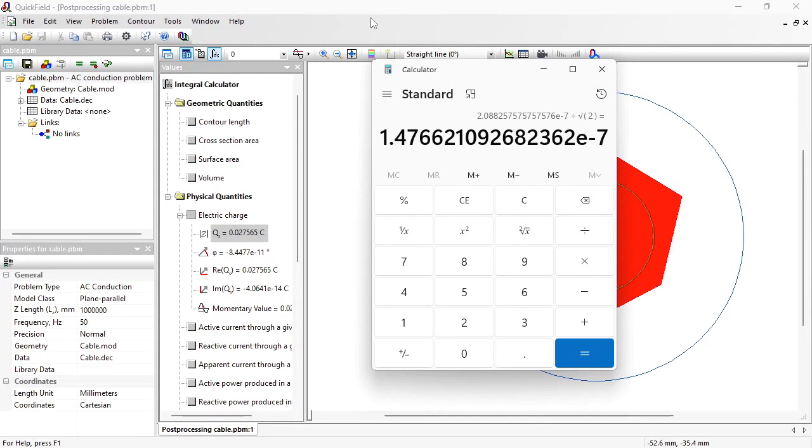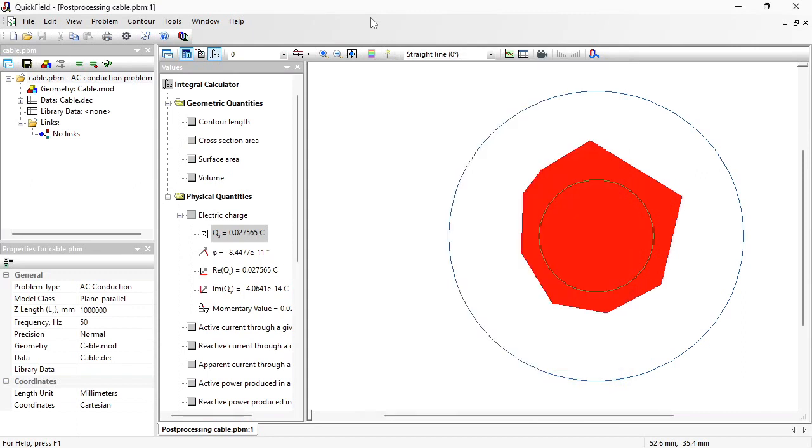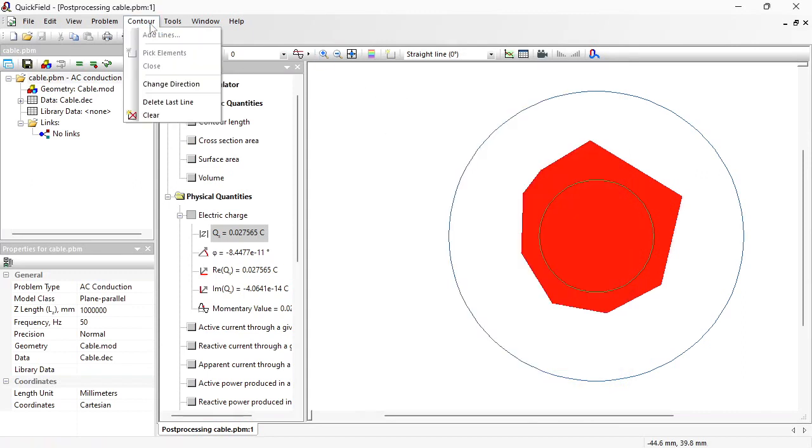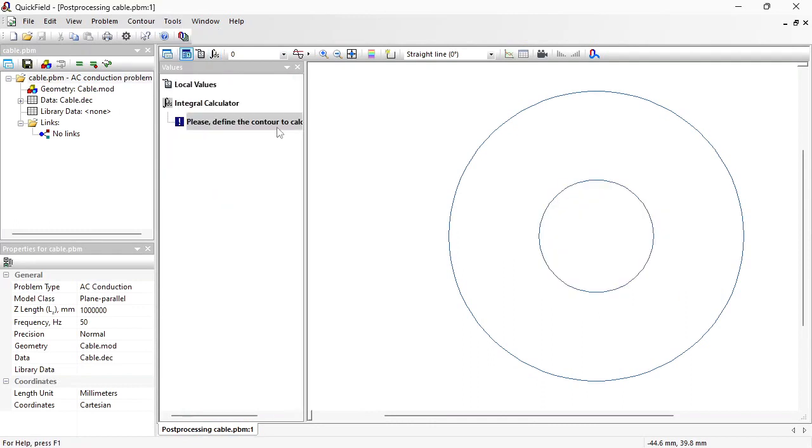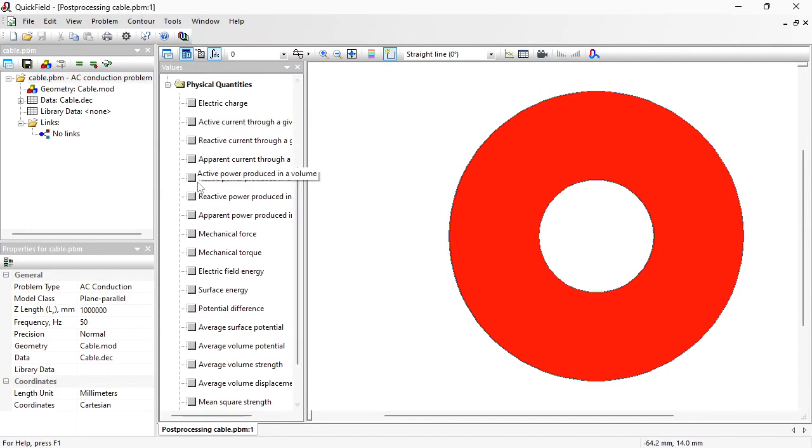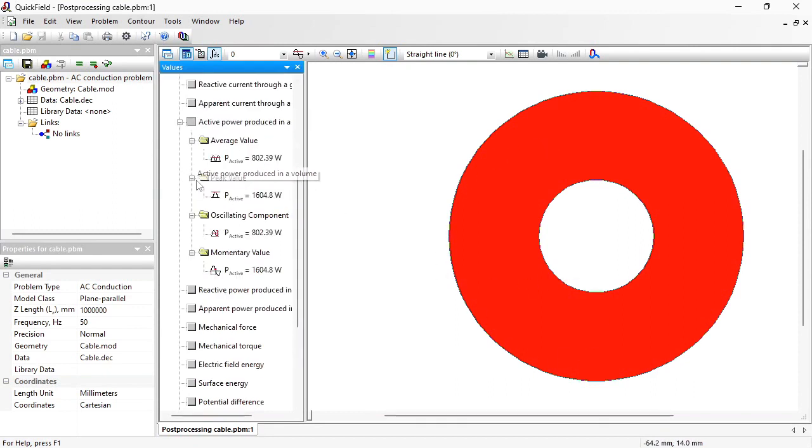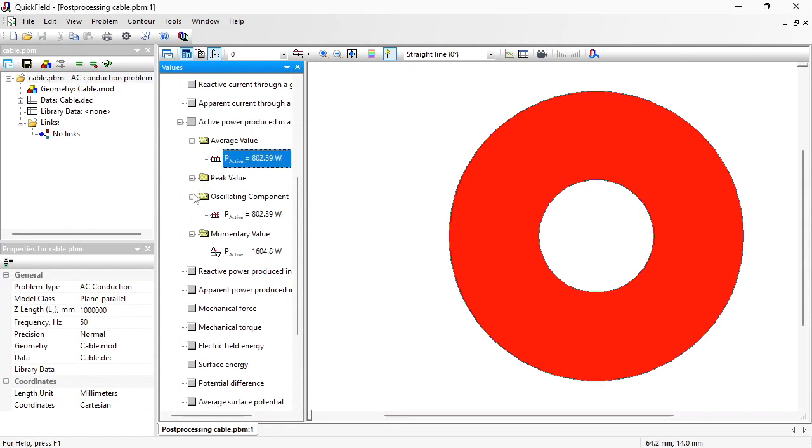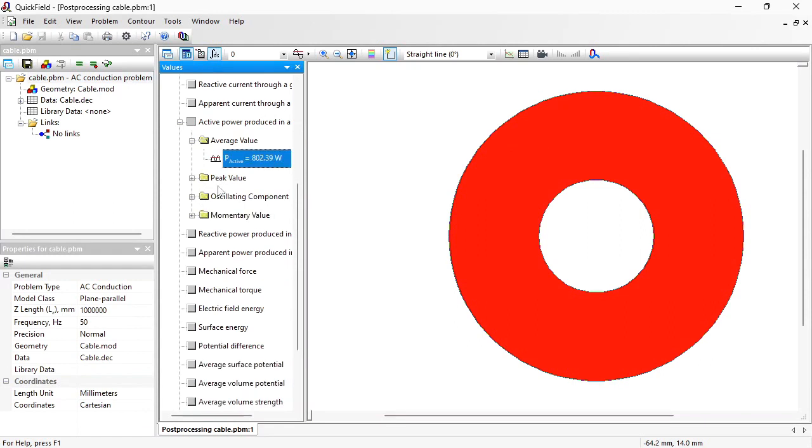Now let's calculate the losses. Again I am going to use the contour tool. But this time I will select the insulation. Click to select. Go to the integrals. And this is the active power produced in the volume. Again this value is calculated for the one kilometer of the cable length.